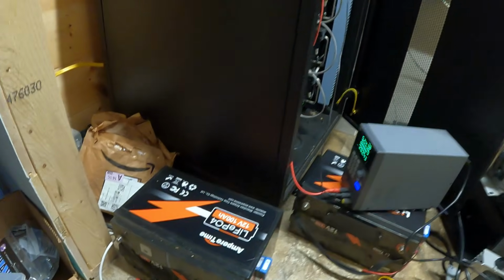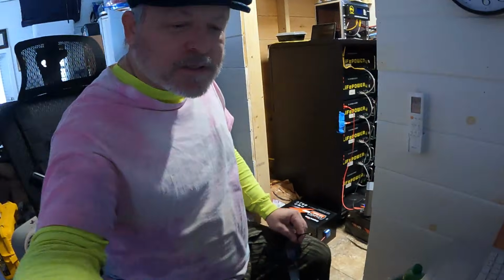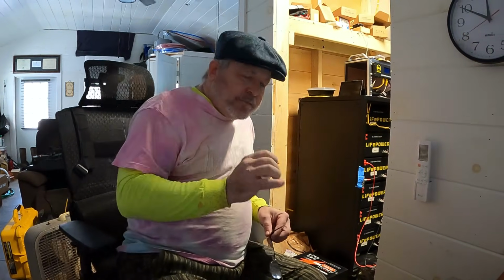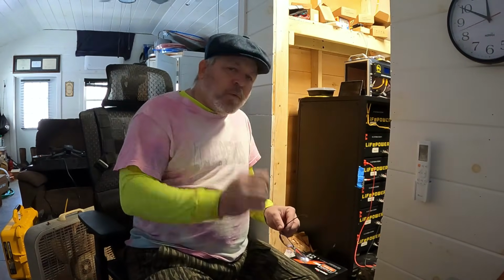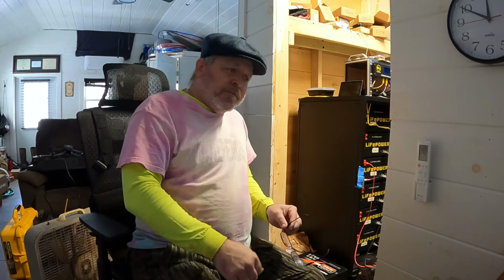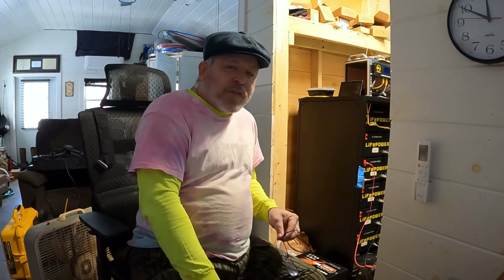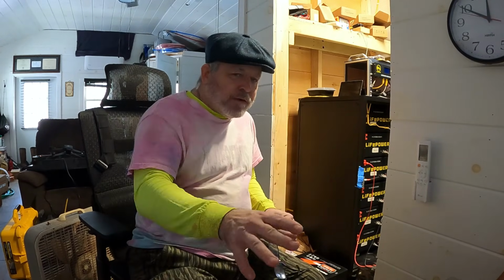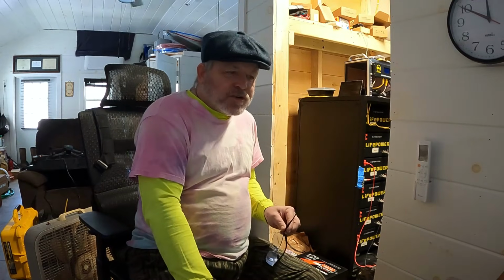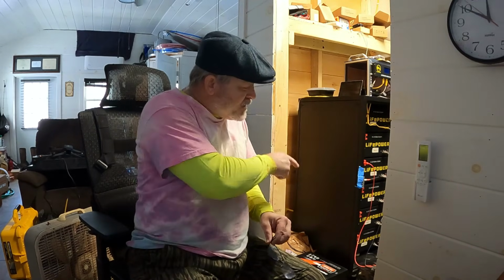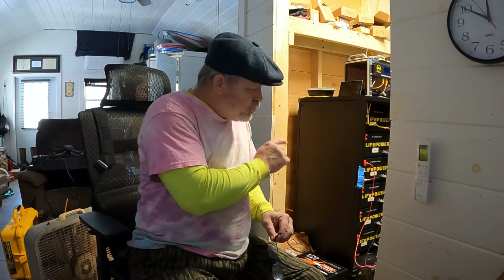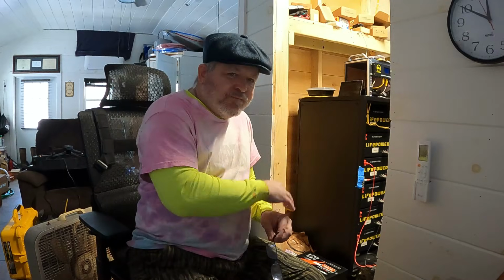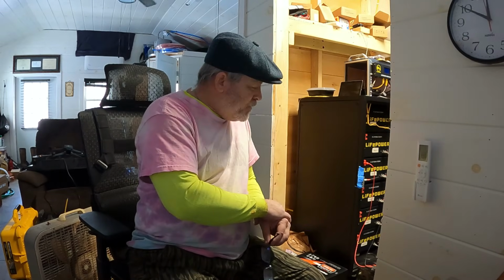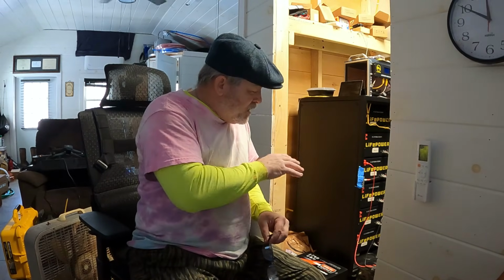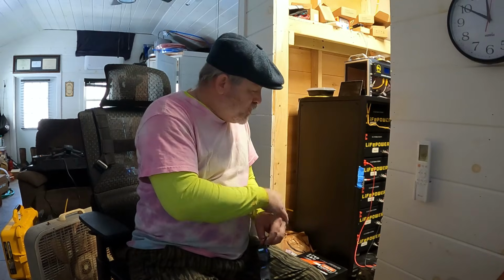So make sure your critical systems have low temp protection and you know it works. And be prepared for them to have to warm up to clear that fault so you can start charging again. Have some way to trickle charge at 5-10 amps with variable voltage — have some way to wake that up.